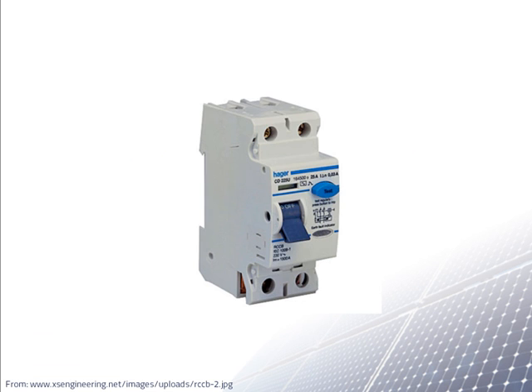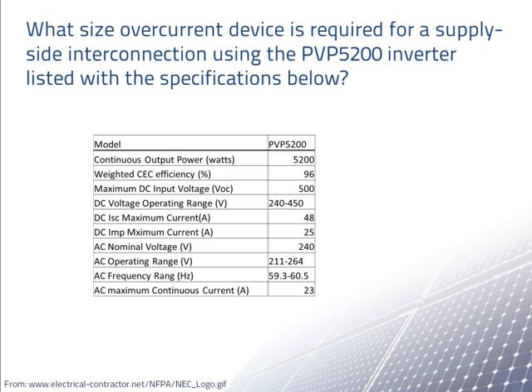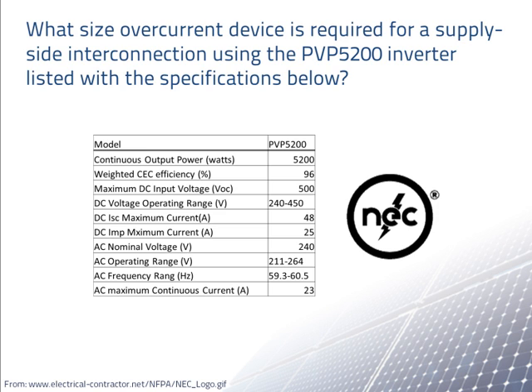An overcurrent protection device prevents conductors or devices from reaching excessively high temperatures due to very high currents by opening the circuit. In this example, we are given a specifications sheet of an inverter and shown how to size the overcurrent device according to the National Electric Code.